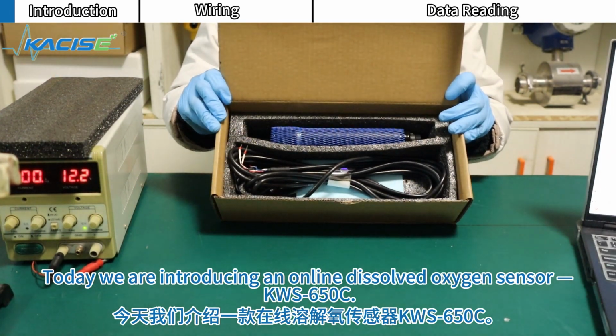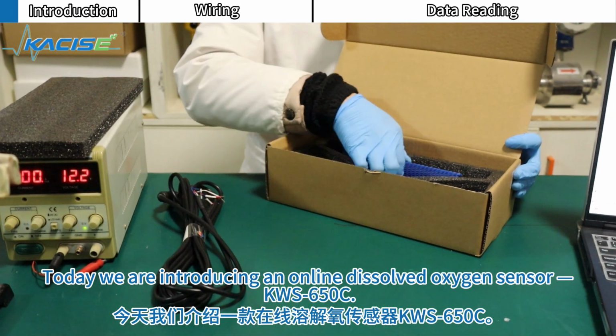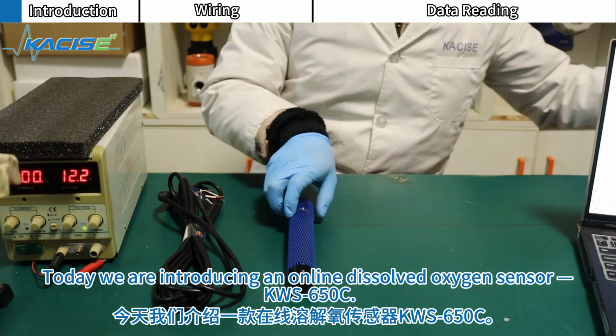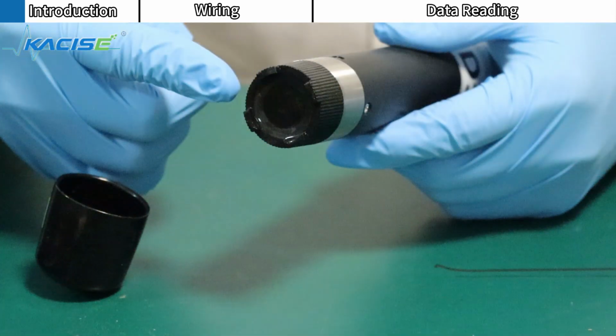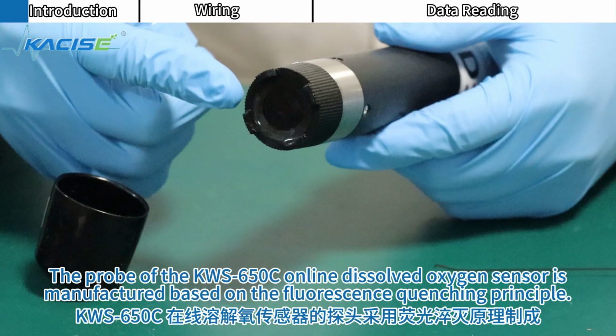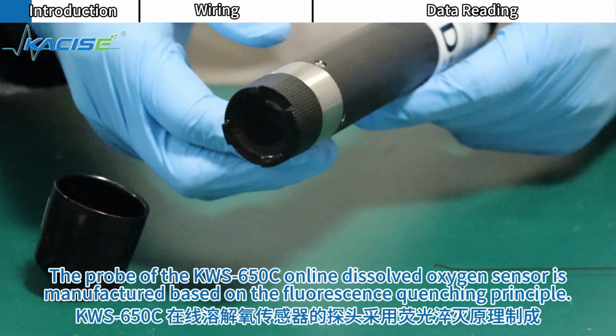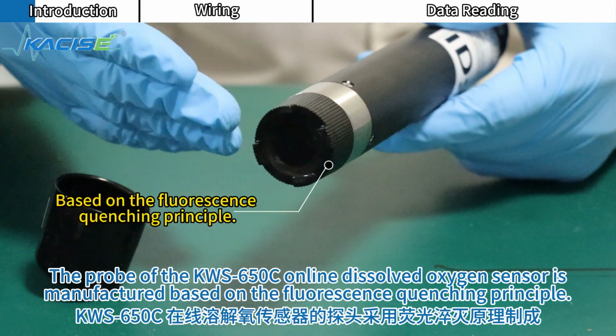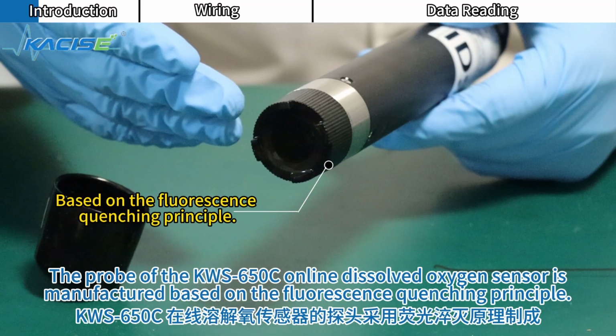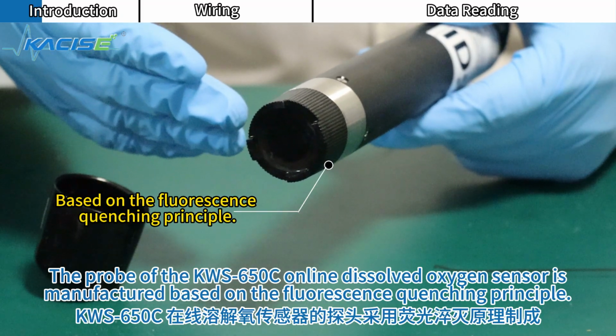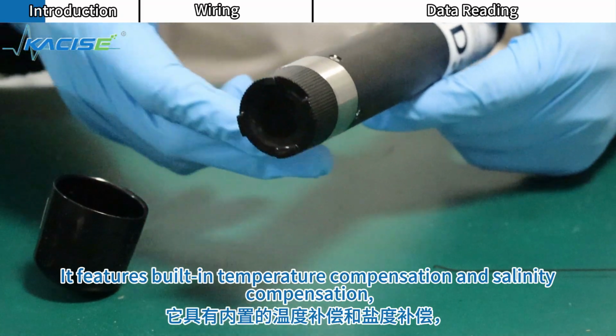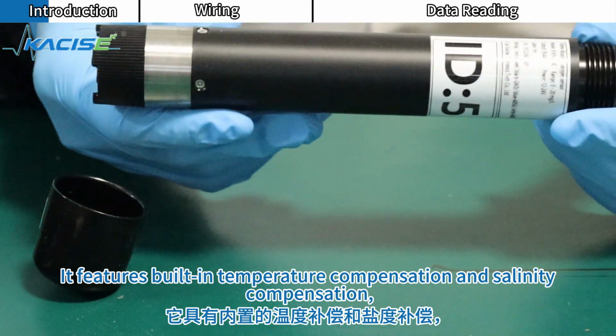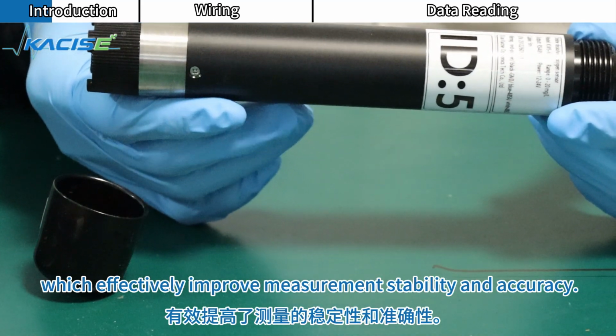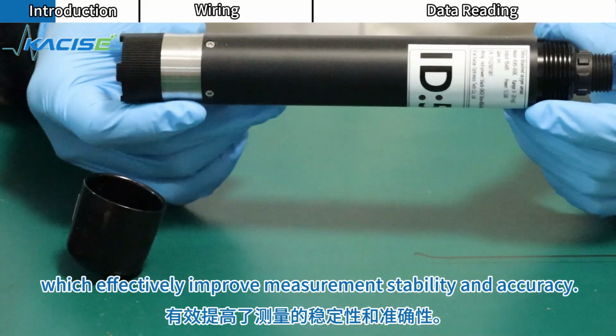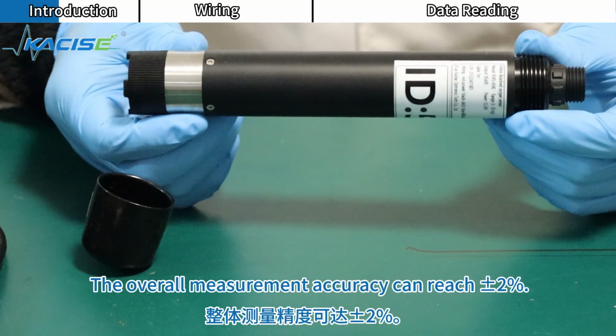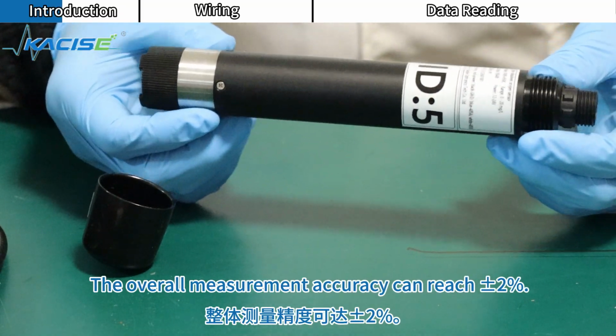Today, we are introducing an online dissolved oxygen sensor, KWS-650C. The probe of the KWS-650C online dissolved oxygen sensor is manufactured based on the fluorescence quenching principle. It features built-in temperature compensation and salinity compensation, which effectively improve measurement stability and accuracy. The overall measurement accuracy can reach plus or minus 2%.